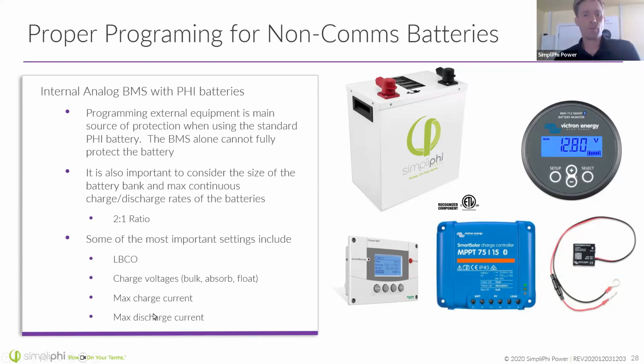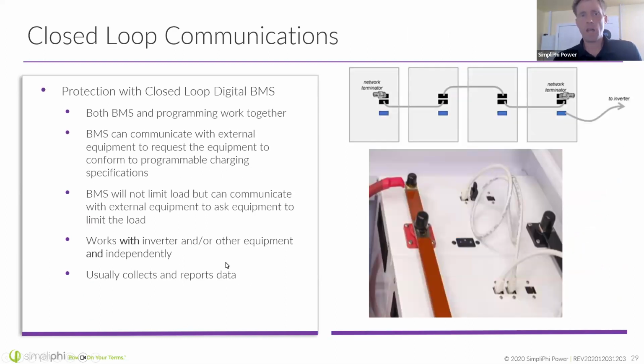Okay, so let's move on. The maximum charge and discharge current is dependent on the battery. I'm going to show you those in a second. I also want to show you closed loop communications. There are a couple of things I want to point out with closed loop communications and common mistakes when installing these batteries with the communications equipment. So first off, there is a cable that is used to allow individual BMS units from individual battery modules to communicate with the other battery modules in the system.